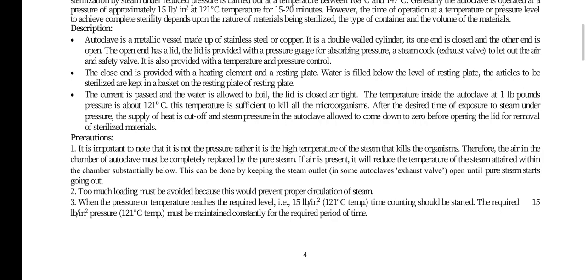The temperature inside the autoclave at 15 pounds pressure is about 121 degrees centigrade. This temperature is sufficient to kill all the microorganisms. After the desired time of exposure to steam under pressure, the supply of heat is cut off and the steam pressure in the autoclave is allowed to come down to zero before opening the lid for removal of sterilized materials.